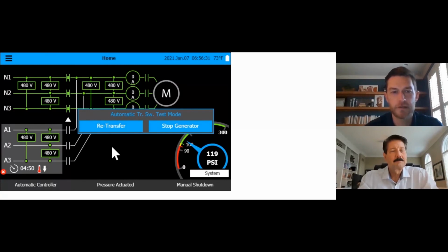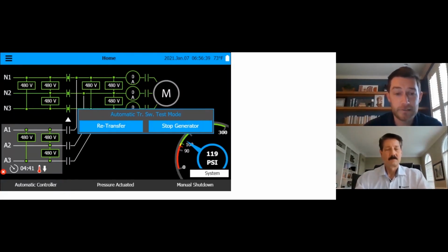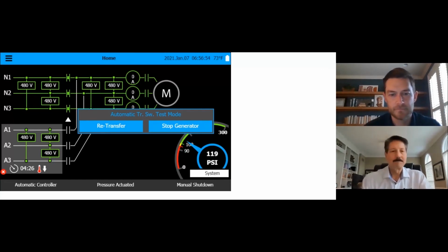Like if you're running your pump at the time and you're trying to transfer over to the alternate power while it's flowing, that button is not to be used for that. It actually won't do anything. If you push the button during flow, it will not start the generator. So the way to do that is to kill power. Exactly. That's a very good point.